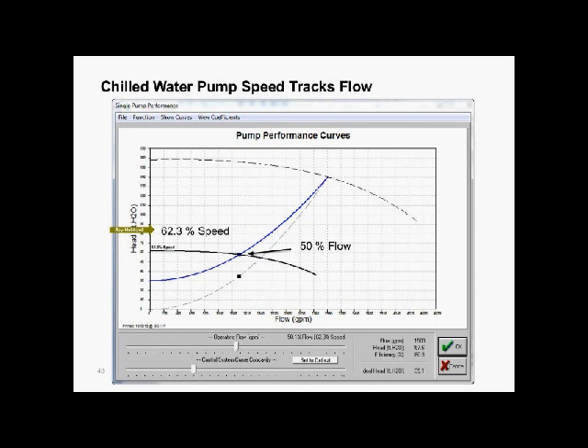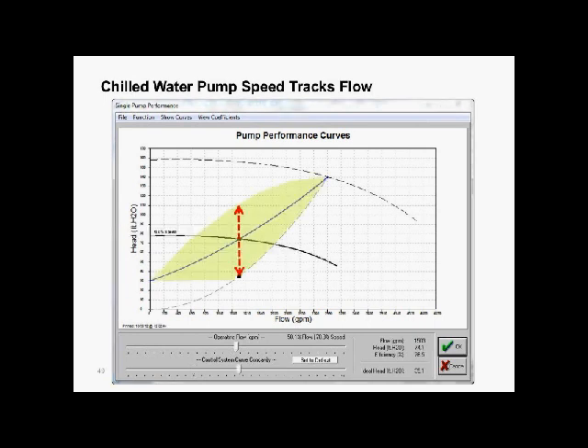It even gets more interesting because it's not really a curve it follows, it's an area. What happens with chilled water pumping is that I could be operating down here or anywhere in between. If I'm up here, I'm in the perfect condition, following as ideally as I can. All the loads in the building are exactly the same percent load. So if I'm at 70% load on one coil, I'm at 70% load on all coils. But that's not real. If the coils far away from the plant are the most active, the highest loaded, and the ones closer are not, I'm going to be operating up here in the head area. If the coils close to the plant are more active, then I'm going to be in the lower part of the area.